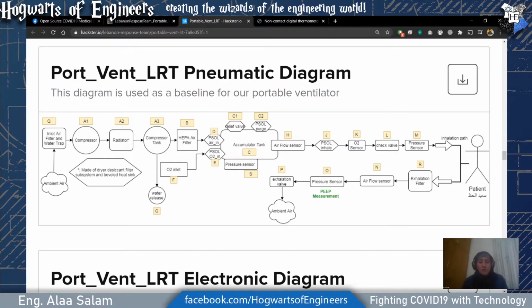Then we compress it. An air compressor basically gives a push of air at a specific pressure. Usually it's 4 bar, because this is the kind of pressure we need on a ventilator so it can give high pressure for the patient if we need it in one of the ventilation modes.